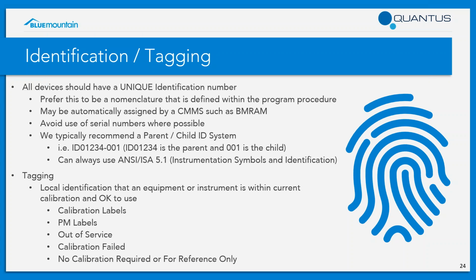If you are using a CMMS database to generate sequential numbers in your system, we're typically going to recommend a parent-child ID number system. So for the example on the slide, we have ID number 1234, which would be your parent. Say that's an autoclave. And just like one parent can have many children, an autoclave can have many instruments. So your parent ID would be that 1234, and then we would use a 001 or 002 control number for all the other respective instrumentation that is on that. In the case where you have just a single device, such as a balance or a scale or a pipette, that would just receive the parent ID.